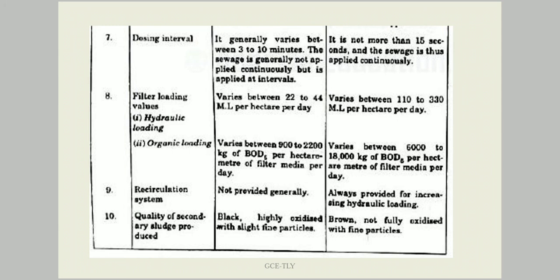The filter loading values show that hydraulic loading varies from 22 to 44 ML per hectare per day for conventional filters and 110 to 330 for high rate filters. Organic loading varies from 900 to 2200 for conventional trickling filter and 6000 to 18,000 kg of BOD per hectare-meter of filter media per day for high rate trickling filter. Recirculation is not provided in conventional trickling filter but is always provided in high rate trickling filter.